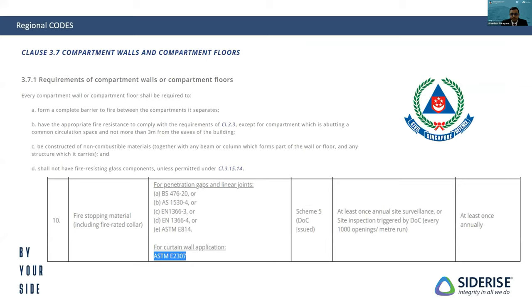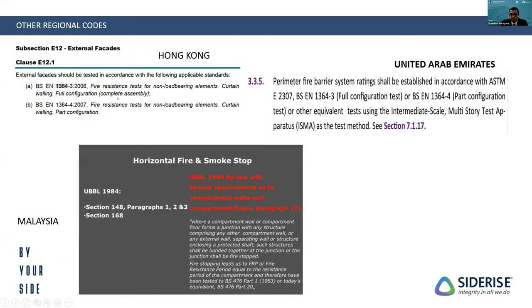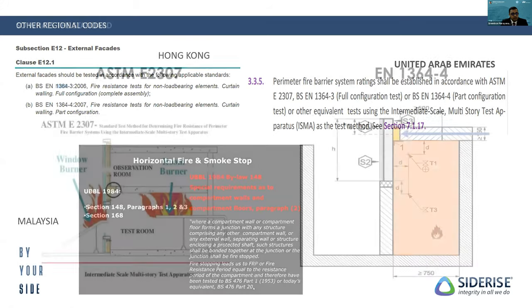What do the codes say in the region? Singapore requires that a curtain wall product be tested to ASTM E2307, and also requires an annual audit of the manufacturer supplying the system. Hong Kong uses EN 1364. UAE allows either ASTM or EN standards. Malaysia allows a BS standard as per the UBBL.